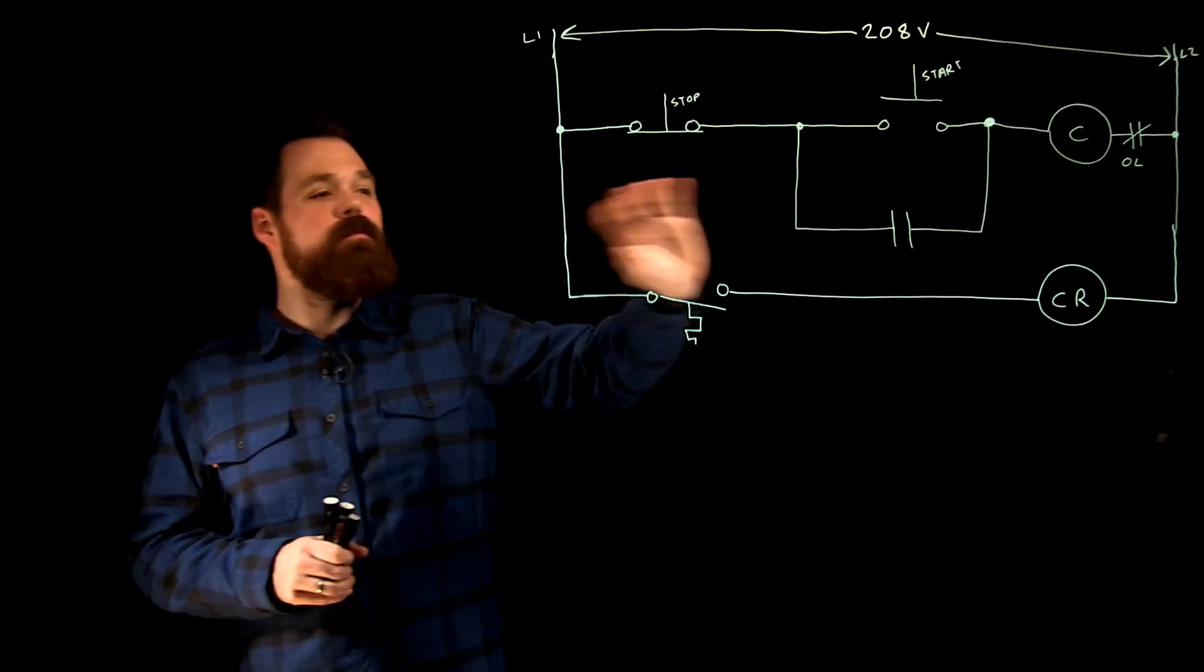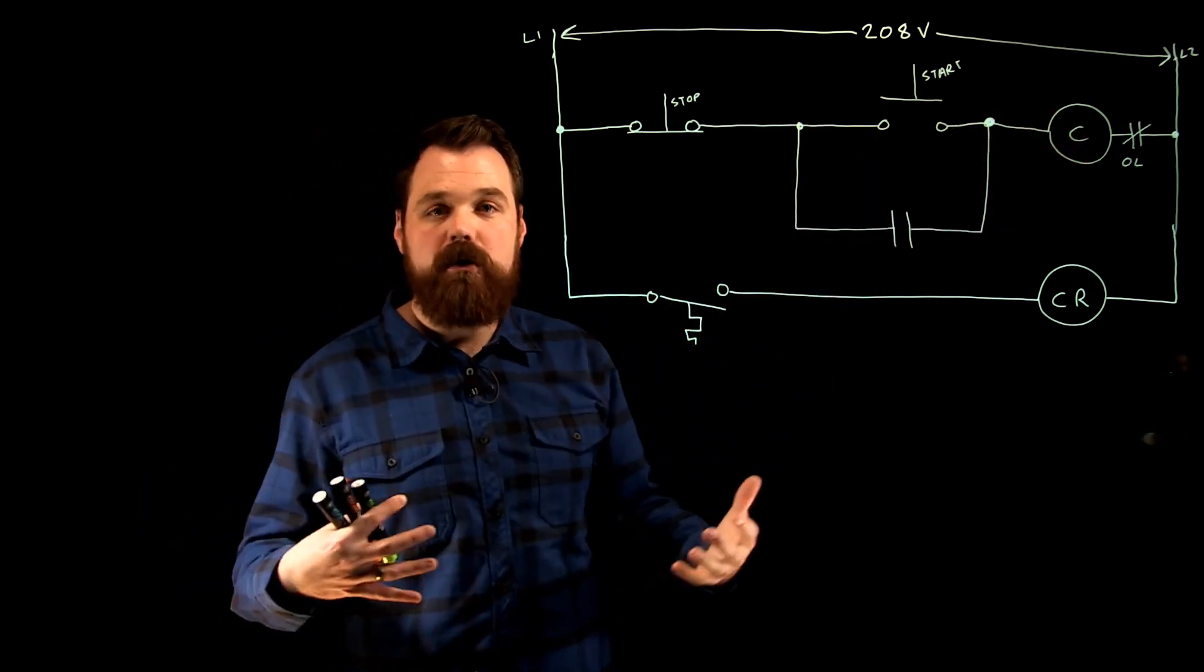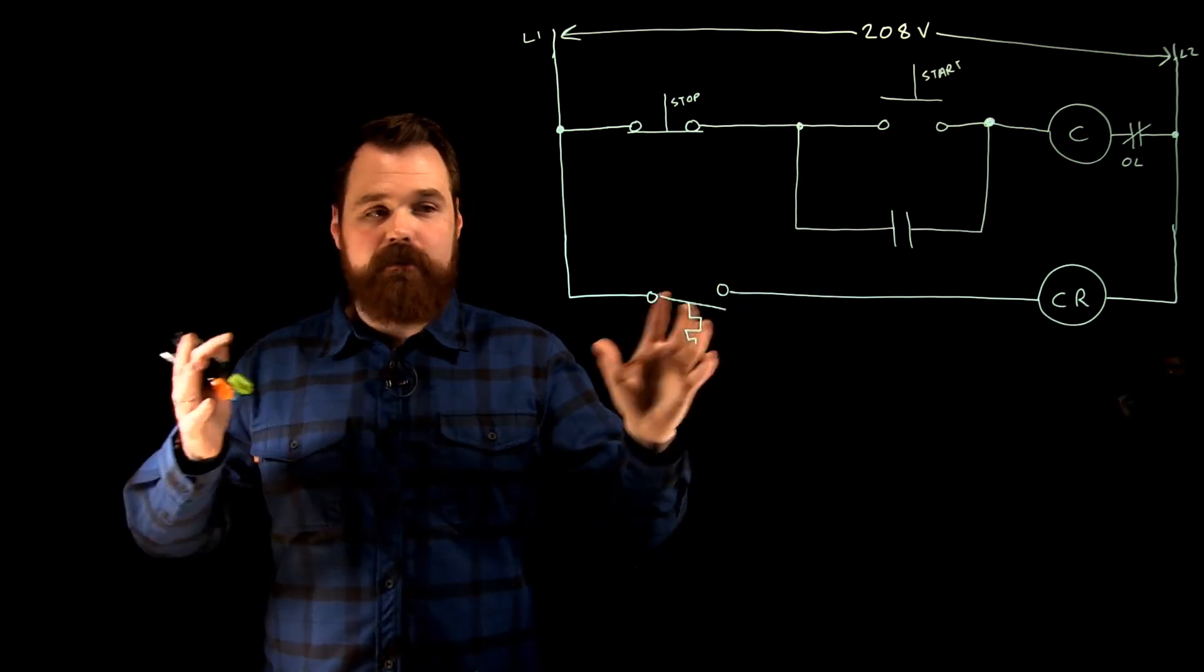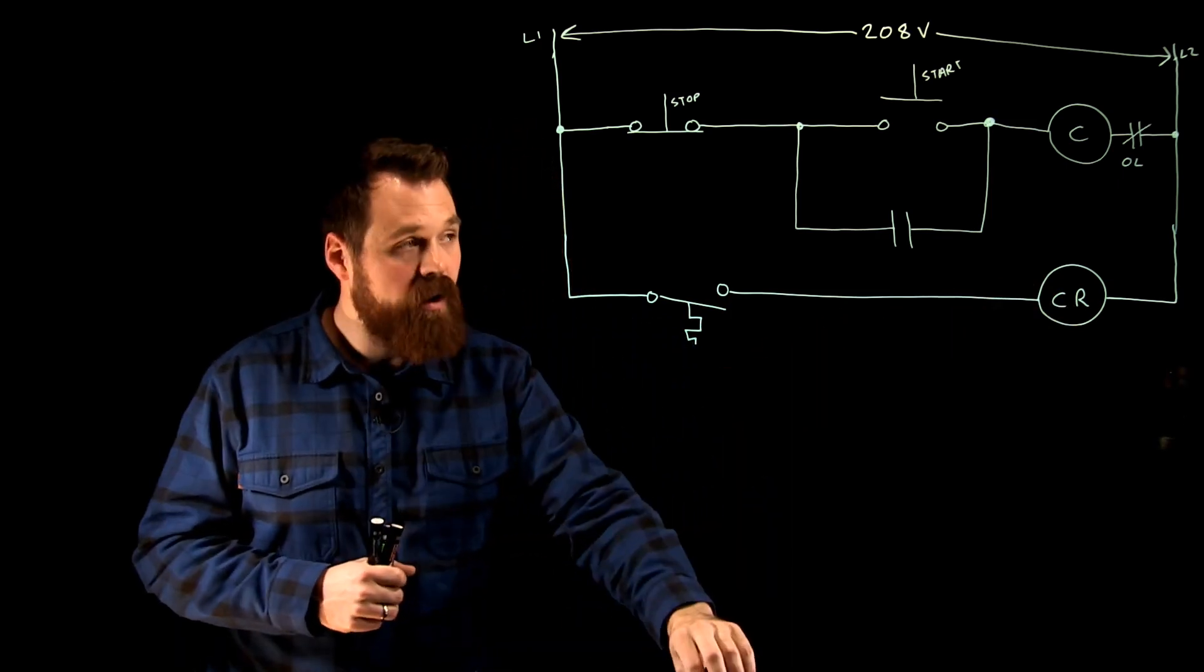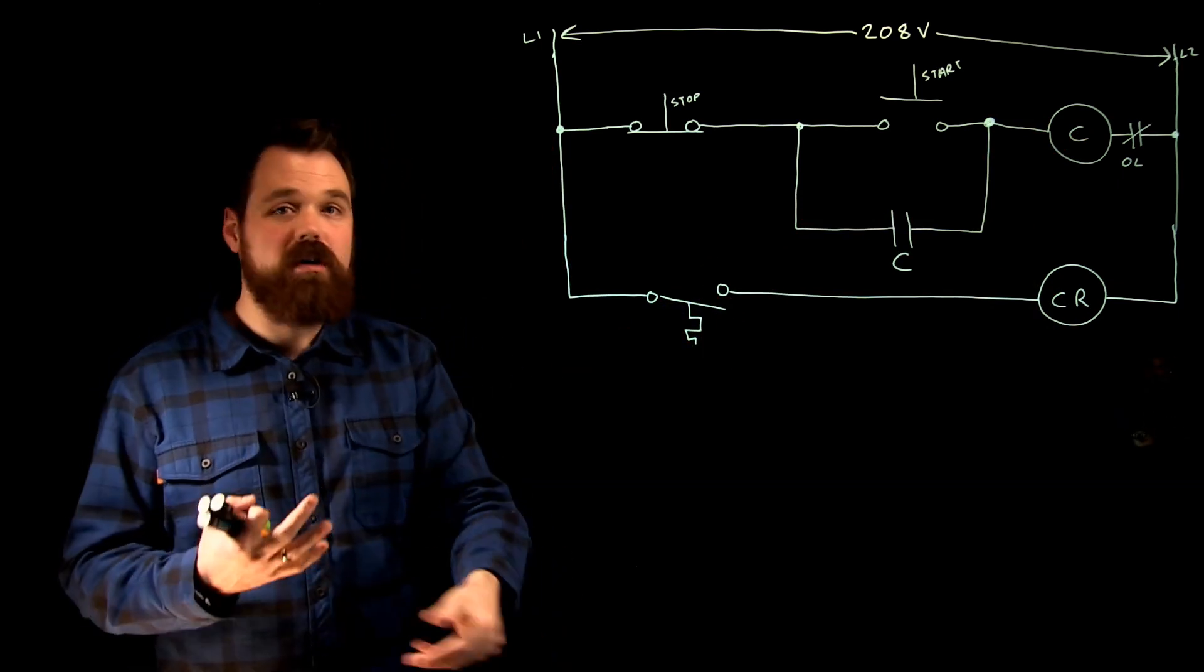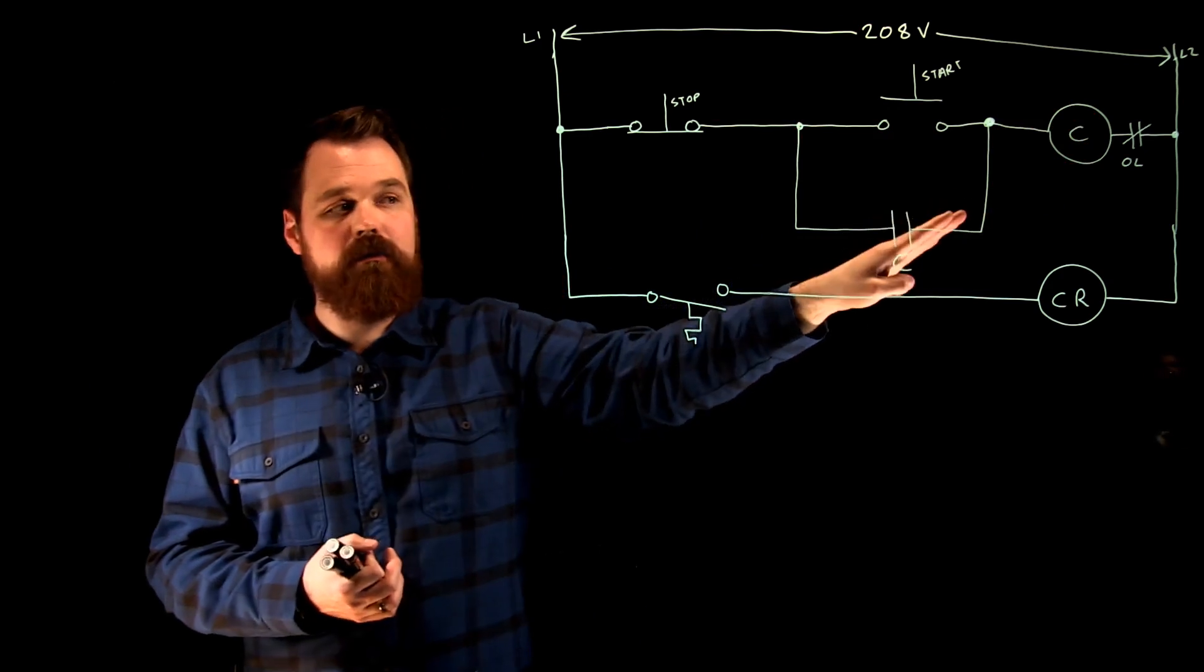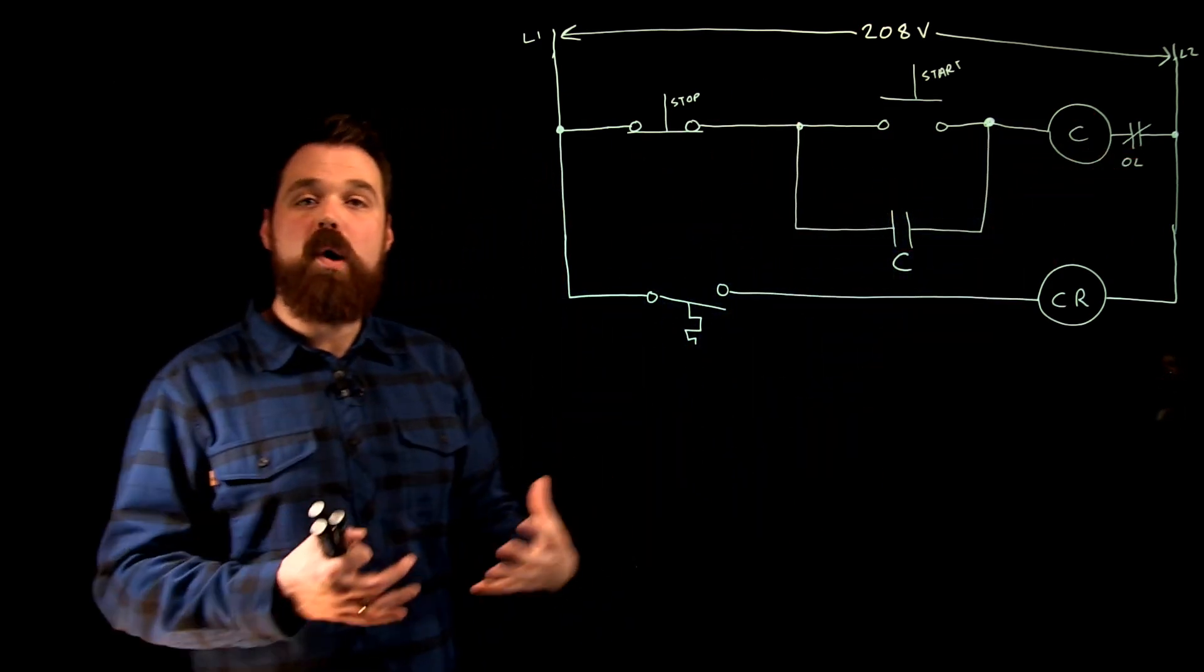So what I've got here is just a simple start-stop station running a contactor to run a motor. And then in addition I have just for sake of conversation a temperature switch which controls a control relay. Now we know our holding contacts are going to be controlled by our contactor. So how this circuit would normally work, we press the start button, contactor would energize, we would close our holding contacts, we would see that path of current and our motor would run.